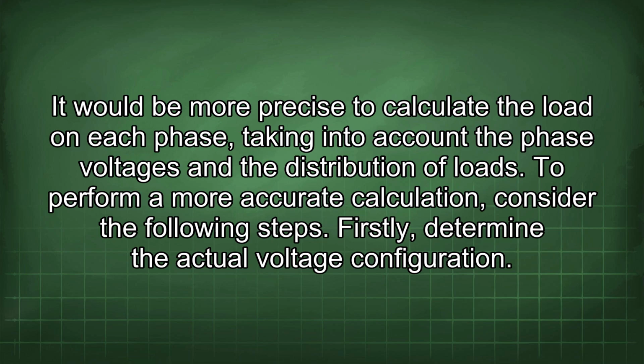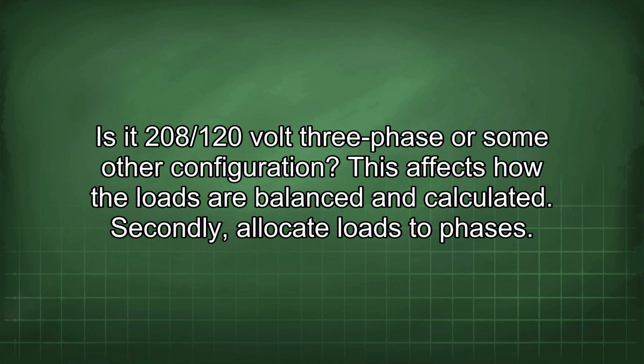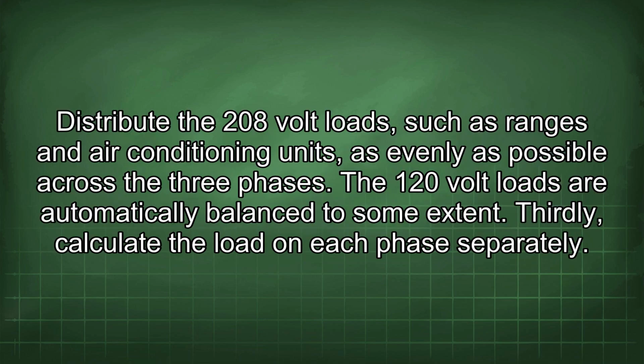Firstly, determine the actual voltage configuration. Is it 208/120 volt three-phase or some other configuration? This affects how the loads are balanced and calculated. Secondly, allocate loads to phases. Distribute the 208 volt loads, such as ranges and air conditioning units, as evenly as possible across the three phases. The 120 volt loads are automatically balanced to some extent.